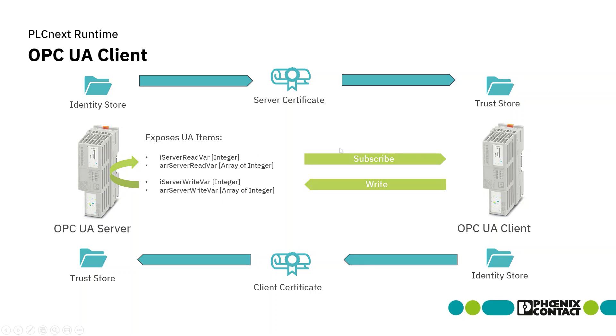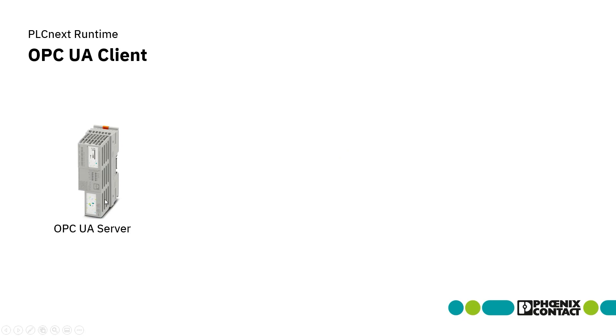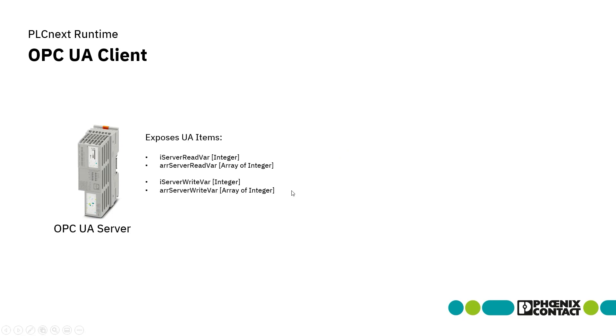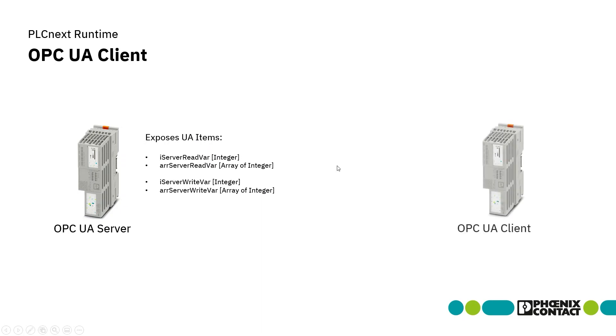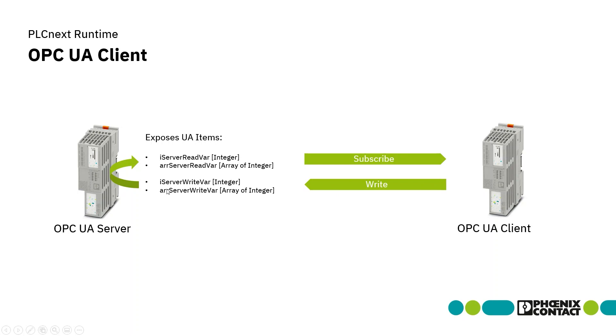Okay, let's start. Well, in this demonstration setup, we are just using a PLCnext control as OPC UA server, in that case a 2152. But of course, this could be any other device like an energy meter or other smart devices which implements a UA server. However, this server does expose a few UA items for the read direction and for the write direction. On both variants, we are using each an integer value or an array of integer. For the client, we are using a 2152 as well with activated OPC UA client functionality. The client will write and subscribe those values. Basically, this implements a round trip. So if we write on these variables, they are copied internally on the server and read back for the UA client. Well, very simple setup and the configuration is also that simple.